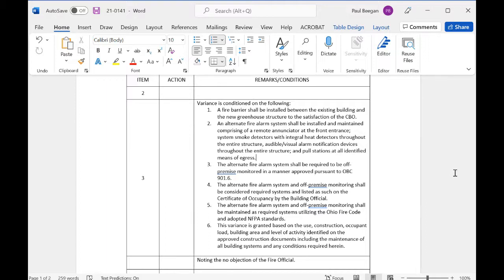Number three, the alternate fire alarm system shall be required to be monitored in the manner approved pursuant to OBC 901.6. The alternate fire alarm system and off-premise monitoring shall be considered required systems and listed as such on the certificate of occupancy by the building official. Number five, the alternate fire alarm system and off-premise monitoring shall be maintained as required systems utilizing the Ohio Fire Code and adopted NFPA standards. Number six, this variance is granted based on the use, construction, occupant load, building area, and level of activity identified on the approved construction documents, including maintenance of all building systems and any conditions required here.